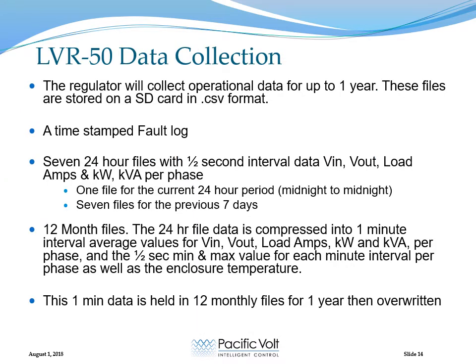The regulator collects operational data for up to a year. There are 3 types of files. There's a time-stamped fault log. There's what we call 24-hour files, which are half-second interval data, and we store 7 of those. So you can get this data file for the last 7 days. And we also store what we call month files, which take the half-second interval data and derive a 1-minute average value, as well as retaining the minimum and maximum value from the half-second data. And there are 12 months of these. At the end of a year, they start to overwrite the month files.